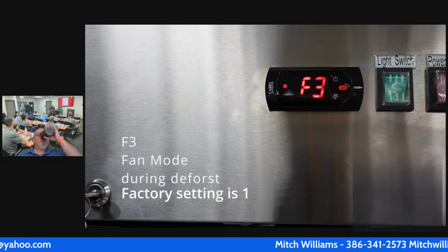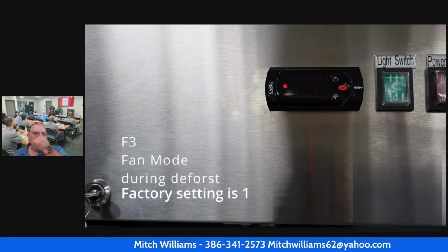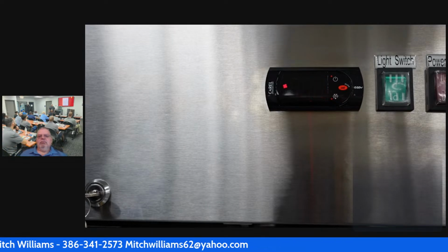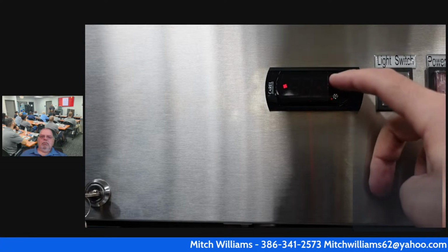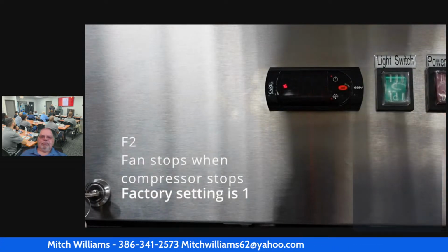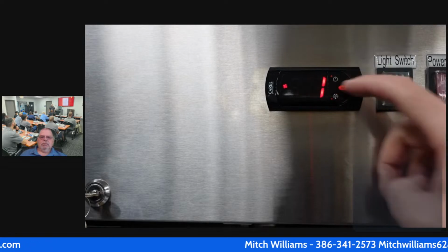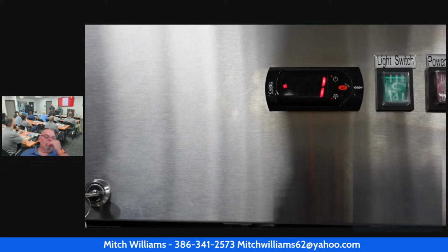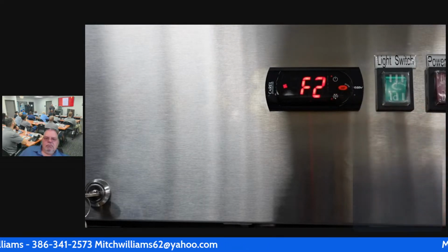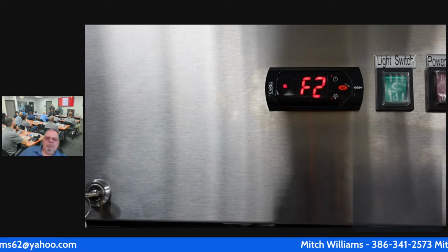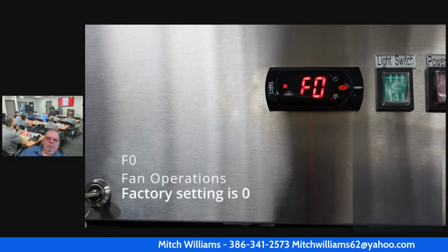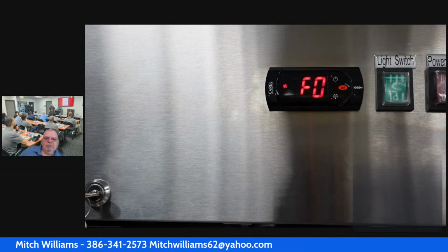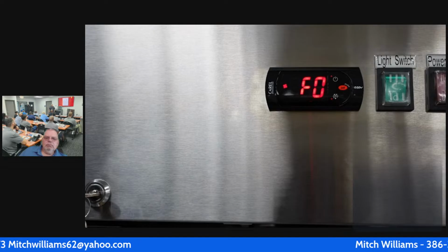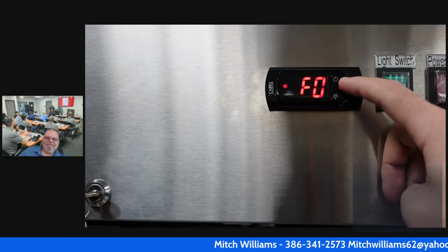The first parameter you'll see is F3. The F3 indicates the fan mode during a defrost. The factory setting is 1. If you want the fans to run during a defrost cycle, set that parameter to 0. The next parameter you'll see is F2. F2 will allow the fan to stop when the compressor stops. The factory setting is 1, and if you want the fans to run when the compressor is off, you can put that parameter down to 0. The next setting we'll see is F0. F0 is the fan operating function, which controls all of the F parameters, or all of the fan parameters. The factory setting on this parameter should be 0.